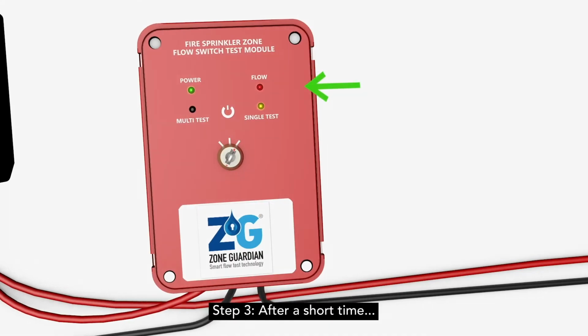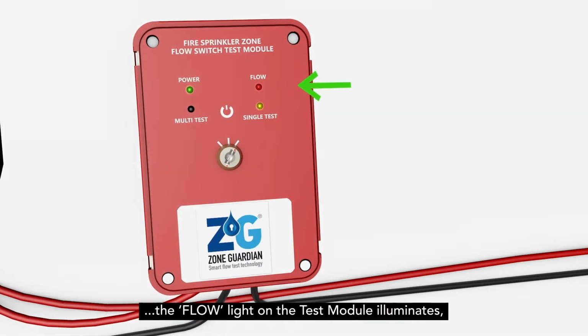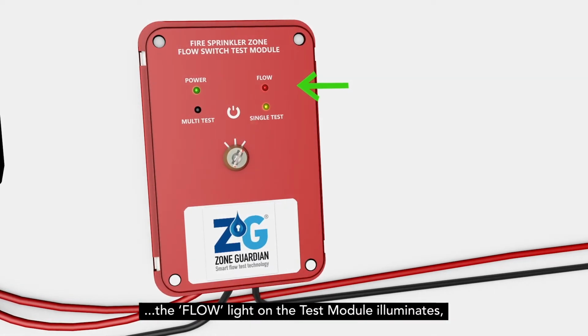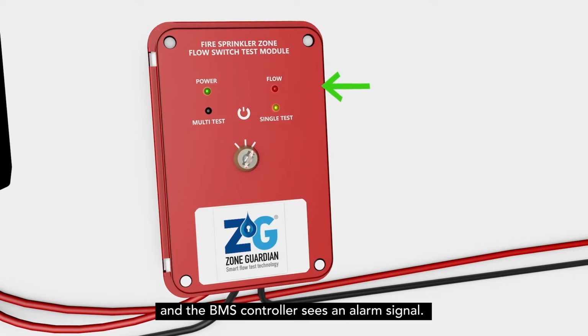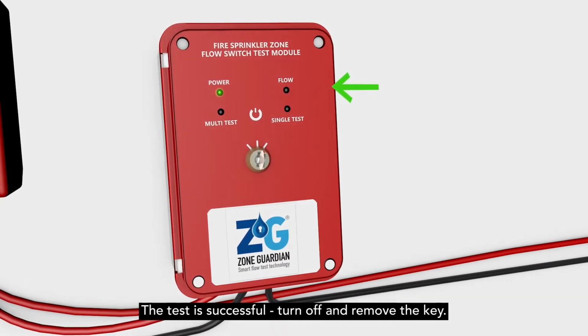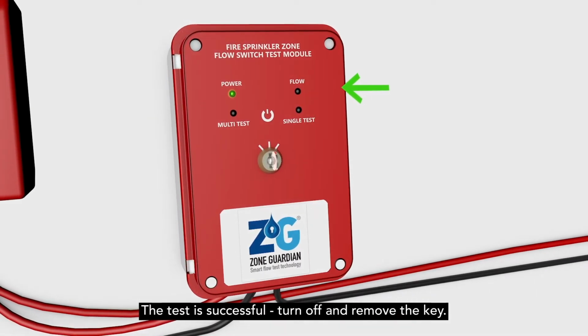Step 3: After a short time, the flow light on the test module illuminates and the BMS controller sees an alarm signal. The test is successful. Turn off and remove the key.